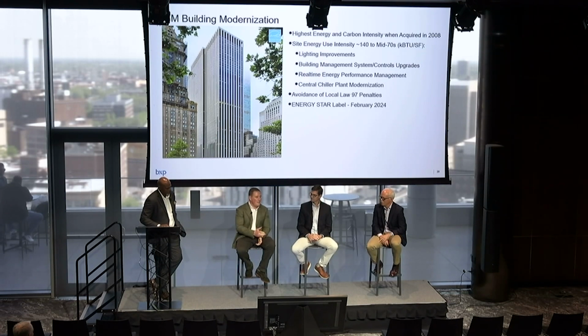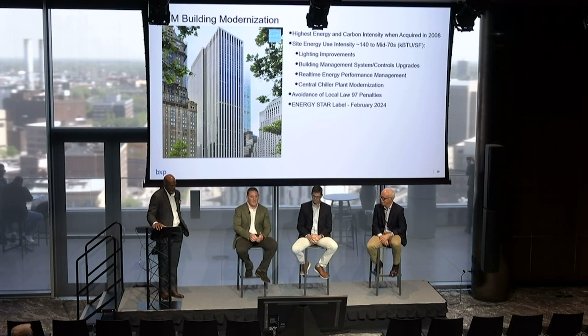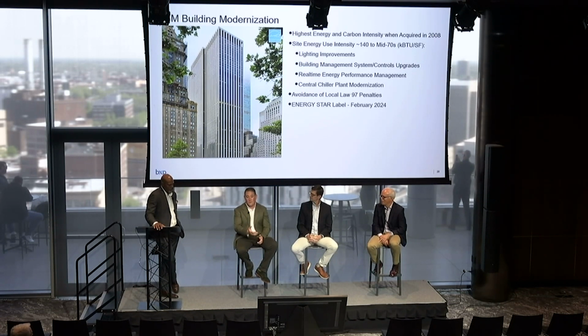Through the acquisition process and underwriting, we knew we had improvements we could make. The biggest chunk was the obvious stuff, lighting, doing complete retrofits. We also did a full ALC building management system upgrade with new controls, and around the same time modernized the chiller plant, replacing old steam absorption chillers with electric drive lines. We had been using steam for cooling, and this is up on the 34th floor of this building.